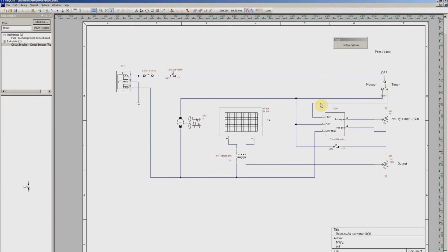So then the power will flow down here into the line input on the timing module, and the time is controlled by this pot, as I mentioned, being connected to the two pot input connectors here, the one for the wiper and the one for the end of the pot. And then the power will go back out the out connector. And that will power up this bus, just like if you flip the manual switch and run the fan through here and run the high voltage transformer.